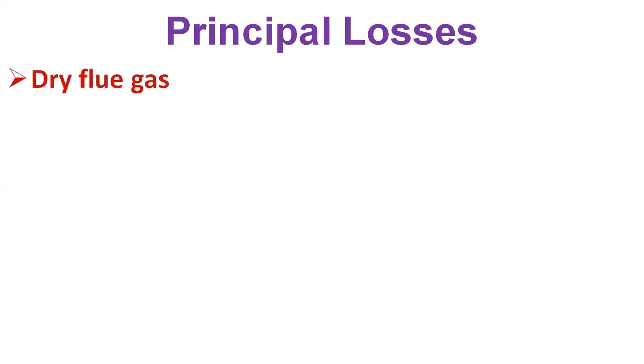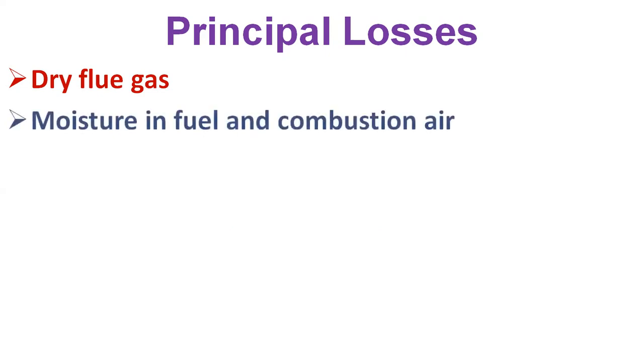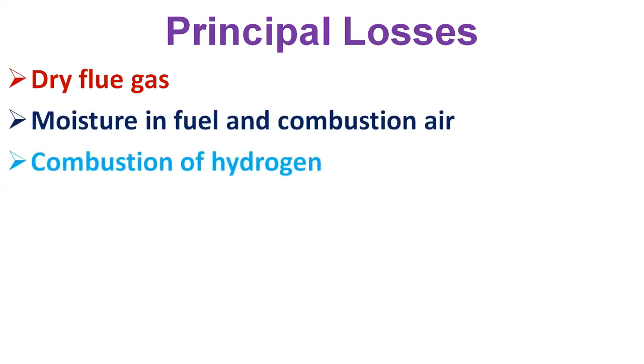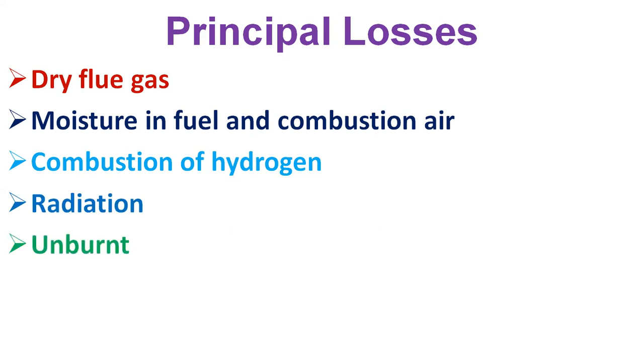The principal losses that occur in a boiler are: loss of heat due to dry flue gases, loss of heat due to moisture in fuel and combustion air, loss of heat due to combustion of hydrogen, loss of heat due to radiation, and loss of heat due to unburnt fuel. Loss due to moisture in fuel and loss due to combustion of hydrogen are dependent on the fuel and cannot be controlled by design.